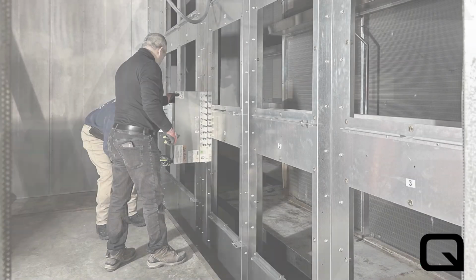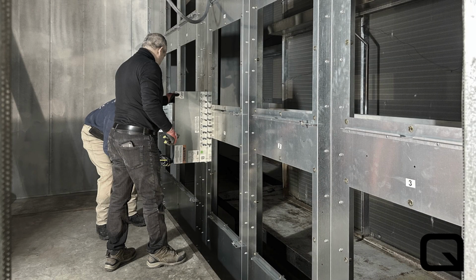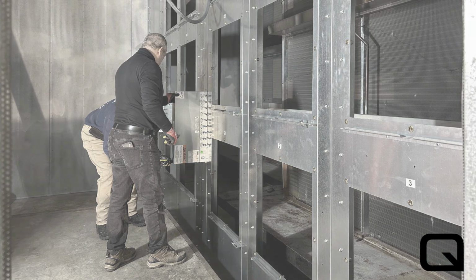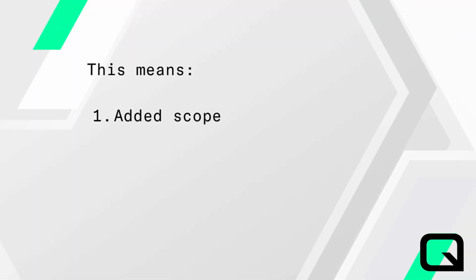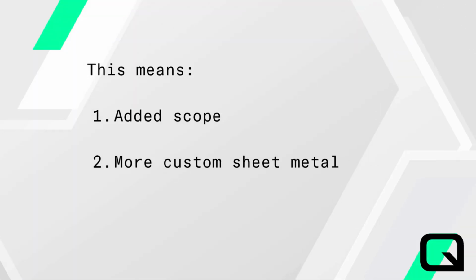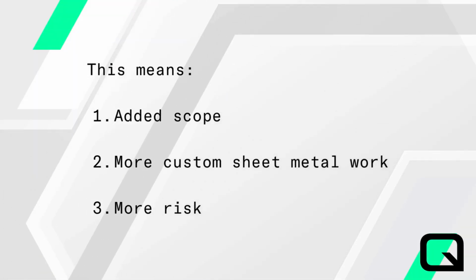Until Q-PAC's multi-motor plenum fan, the frame of a fan would never expand to the total cross-section of the air handler. So when retrofitting a failed fan, for example, it was expected that a new fan would arrive, it'd be installed, and a custom field-installed sheet metal structure would be made to fit the new outlet or to fill gaps outside of the fan. This means added scope to whoever's installing, more custom sheet metal work, and at the end of the day, more risk.